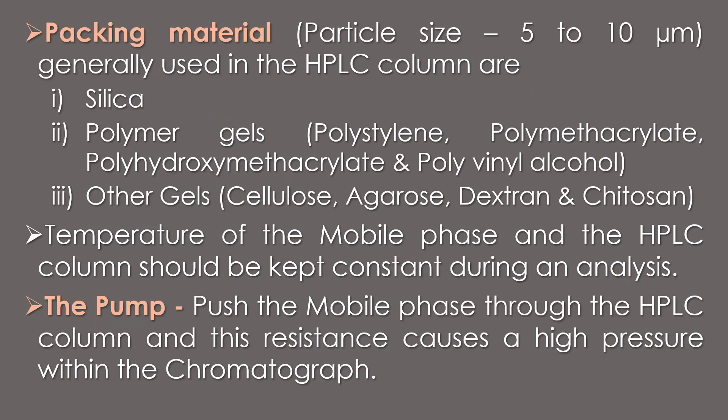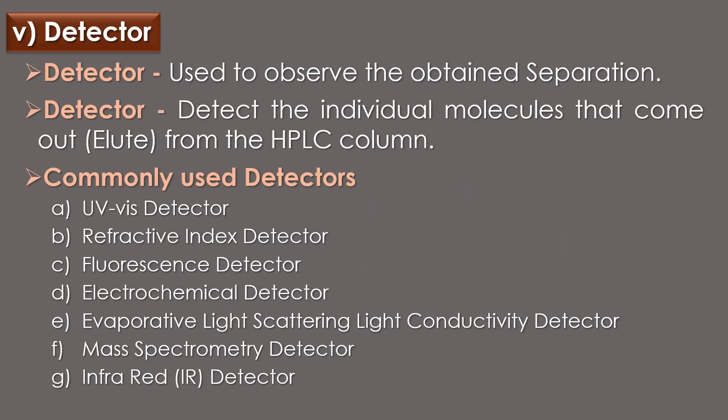The packing material with a particle size of 5 to 10 micrometers generally used in the column includes silica, polymer gels like polystyrene, polymethacrylate, polyhydroxy methacrylate, and polyvinyl alcohol, and other gels including cellulose, agarose, dextran, and chitosan. Ideally, the temperature of the mobile phase and the HPLC column should be kept constant during an analysis. The pump drives the mobile phase through the HPLC column, and this resistance causes high pressure within the chromatograph.